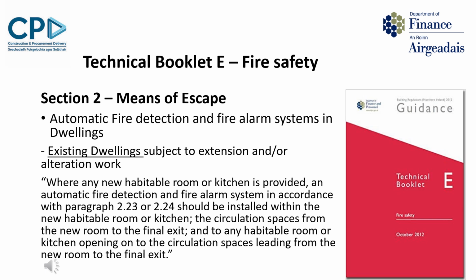In relation to fire detection and fire alarm systems in existing dwellings, there is new guidance to clarify the level of detection coverage expected when an extension and/or alteration work occurs which results in a new habitable room or kitchen being formed. So the guidance clarifies that in these situations, an automatic fire detection and fire alarm system should be installed covering the new habitable room or kitchen, the circulation spaces from the new room to the final exit, and any habitable room or kitchen opening on to the circulation spaces leading from the new room to the final exit. So there will still be an element of assessing provision on a case-by-case basis, but this new guidance should give clarity on what is expected in these types of situations.